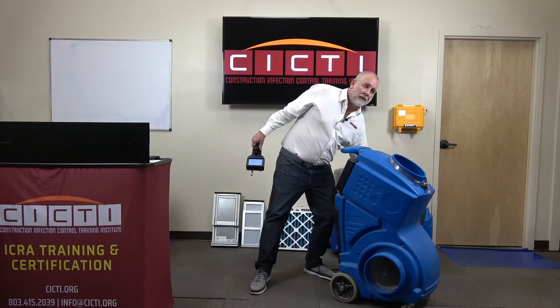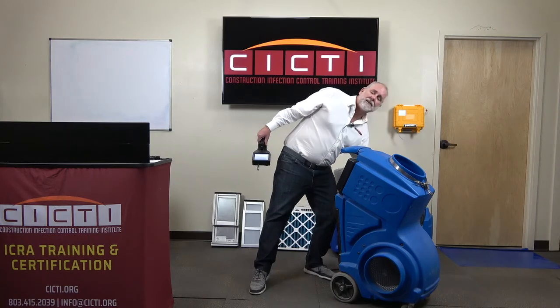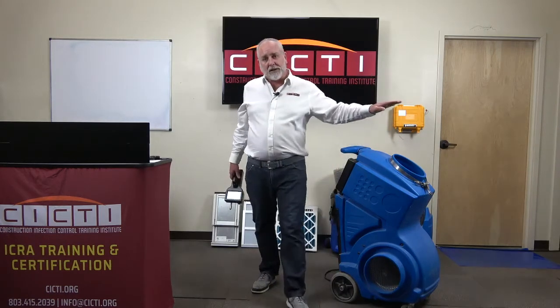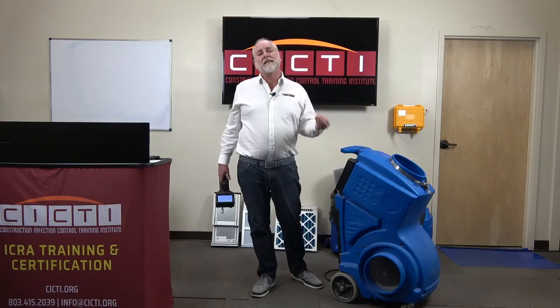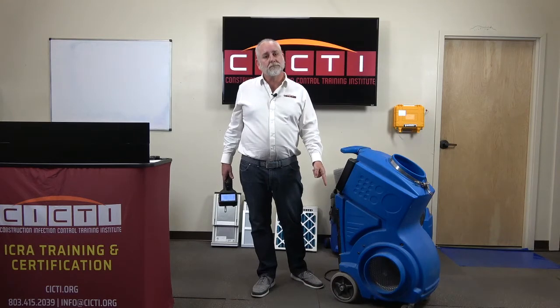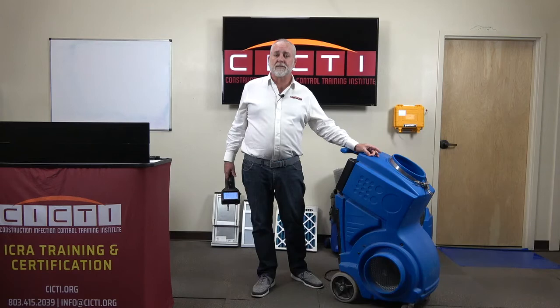It's ready for prime time on your healthcare construction project. Now, we've collected that data. We want to retain that data on this specific device. So in a spreadsheet, I'm going to keep a log, but then I'm also going to put a sticker on this device. The type of information we want to save is the serial number of the device, the date tested, the name of the person that did the testing, the dust concentration that entered the system, the dust concentration that left the system, and then the percent difference between those numbers. And like I said, we're going to put a sticker on this device.